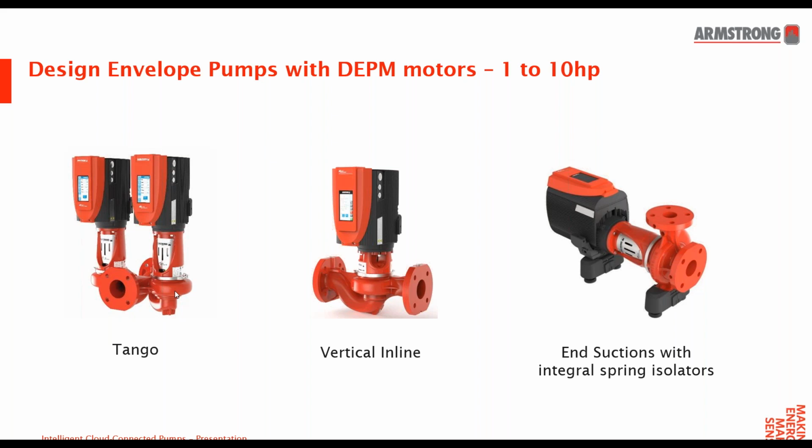I got a quick question for David. If you split the load between two pumps, does that effectively allow you to get better turn down on the VFDs versus a VFD on a pump with twice the horsepower? Yeah, that's a great question, because we've seen a lot of boilers, especially in heating systems in shoulder seasons, that turn down quite a lot. I think it's something like 15 to 1 or 20 to 1, right? So it's actually easier to go with two smaller pumps running in parallel, and if you don't need the second pump, you're just running with the one smaller pump, and you're able to achieve a higher turn down in that sense. So using multiple pumps operating in parallel is really ideal for higher turn downs.